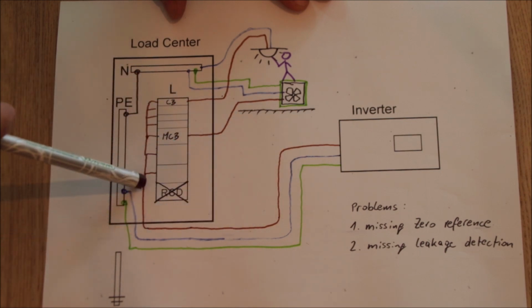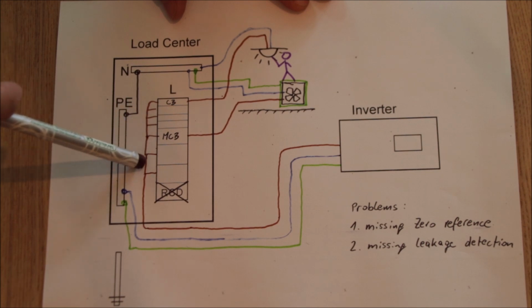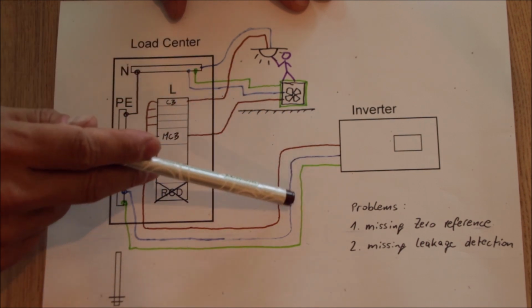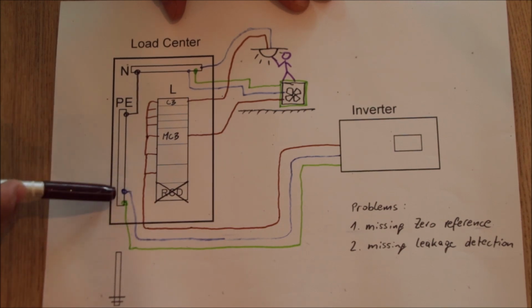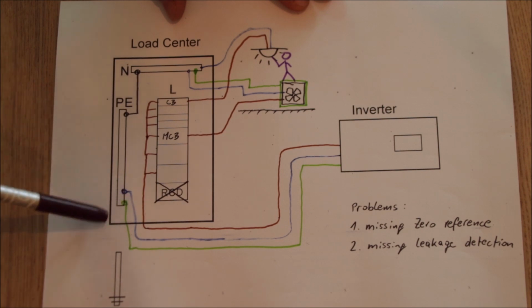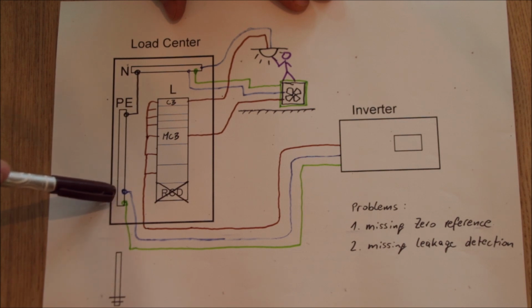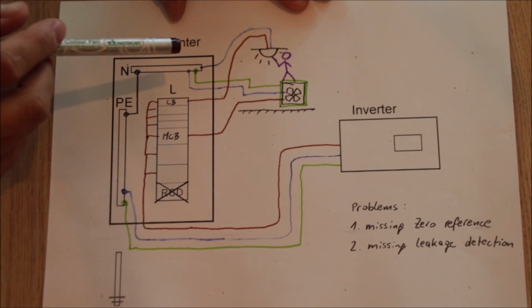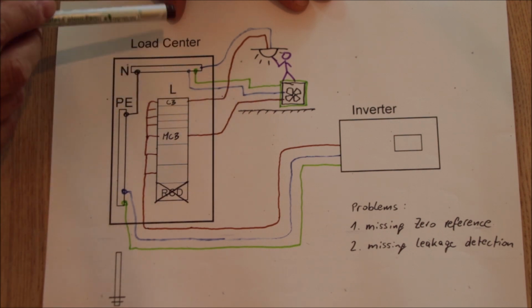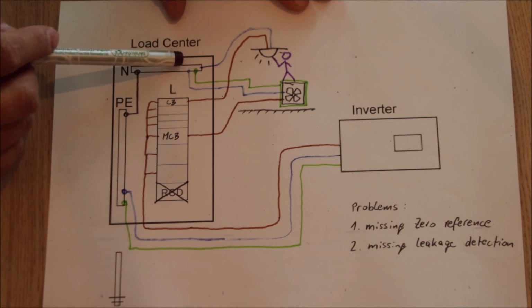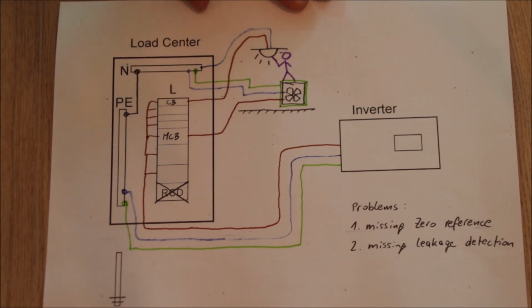So what he did, he connected his 3 output terminals, L going into his circuit breakers, and neutral and ground he has put right onto the first terminal bar, while all the terminal bars, there were 3 inside his panel, all those 3 have been interconnected. So yes, neutral and ground have been bonded, but as you will see, that bond will continue within all the system. So everything else then, when he connected his air conditioner, he just took neutral and PE from the same bars there and went to the appliances.